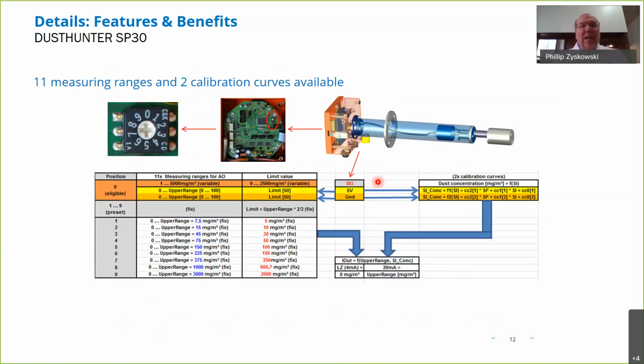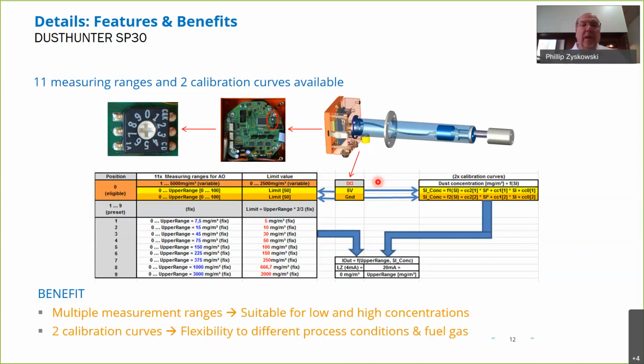A lot of words here on this slide. I'm not going to get into all the details other than what makes this unit so versatile is the fact that there's 2 calibration curves and 11 measuring ranges. All can be selected from the analyzer itself, the monitor itself. You don't need a control unit to do that. And so this gives great flexibility. So high concentrations, low concentrations. It also eliminates the need to do a gravimetric correlation. So you can set these ranges based on what you know, and you can set 2 calibrations based on changes that you anticipate.